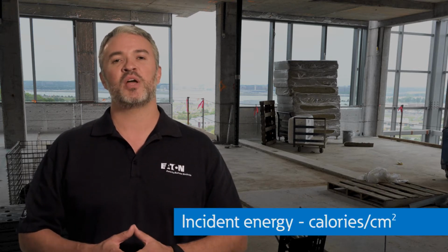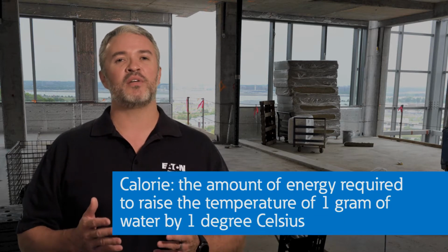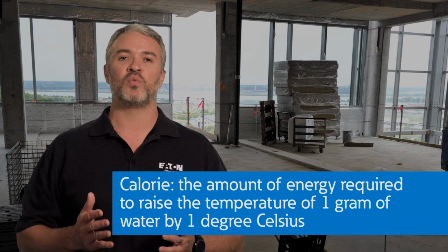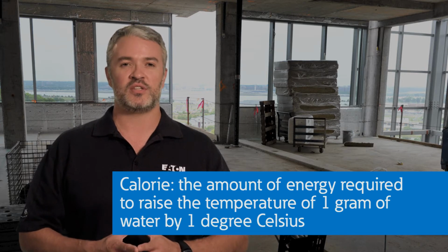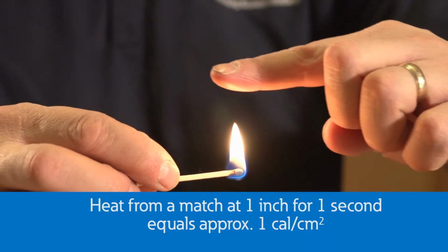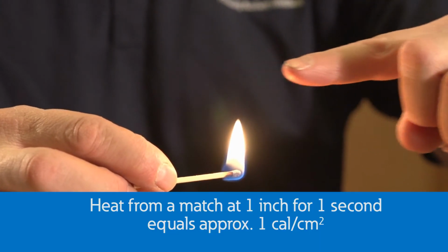The arc flash energy that would arrive on bare skin or on the surfaces of any garments you are wearing is called incident energy and is expressed in calories per centimeter squared. A calorie is the amount of energy required to raise the temperature of 1 gram of water by 1 degree Celsius. 1 calorie of heat is equivalent to holding a match under your finger 1 inch away for 1 second.